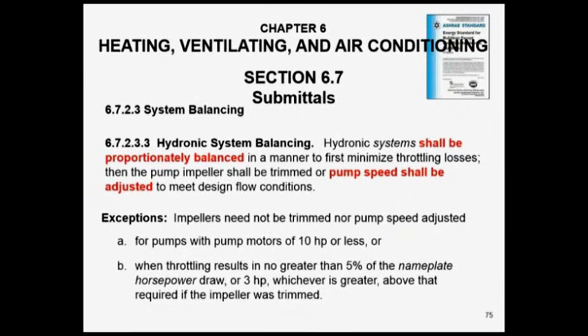What does all this mean? All this means is if you did a true proportioning balance, then the valve would be wide open. It wouldn't be throttled. If we trim the impeller, we could reduce the horsepower. If you didn't want to trim the pump impeller, we could put a variable speed drive on it and slow it down, and we're reducing horsepower.